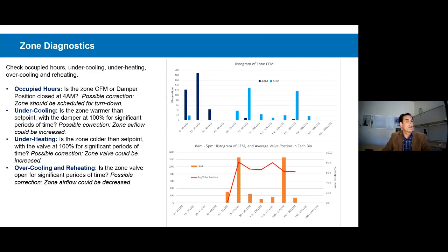And the second histogram that you see on this slide shows the damper and valve position during occupied hours. This particular zone spends a lot of time at 75 to 90 CFM, and then it spends another big cluster of time at 135 to 150 CFM. But notice that the average heating valve position is pretty much always 70% or 80%. Well, that's problematic. Why are we heating? Pretty much across the whole range, the whole spectrum of this zone, why are we doing heating? This is an overcooling and reheating problem.